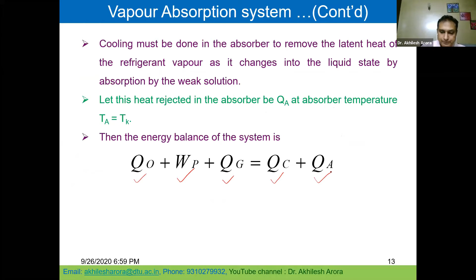Now I would like to highlight the pump work. You know that in a pump we are handling liquid. The pump is installed in the solution line, where the strong solution is flowing through the pump. You will see the diagrams later also. The strong solution may be a water lithium bromide system or an ammonia water system. Whether water or ammonia is the refrigerant, in both cases the specific volume is very small, and the pressure difference could be large.